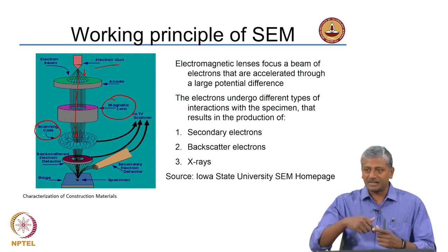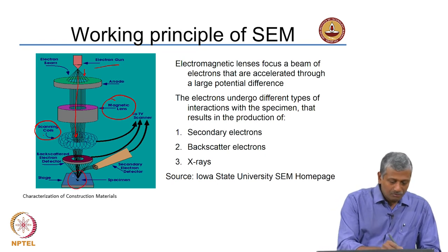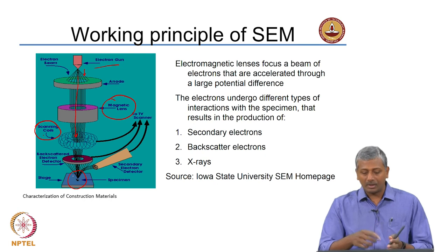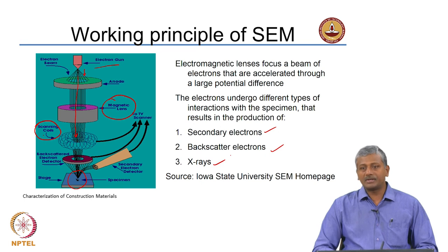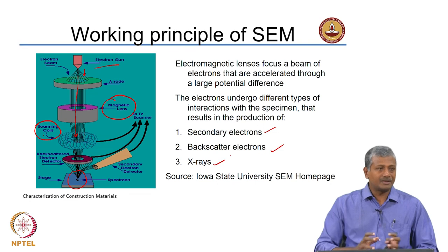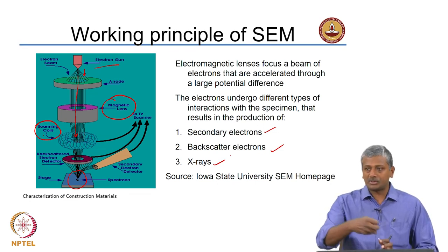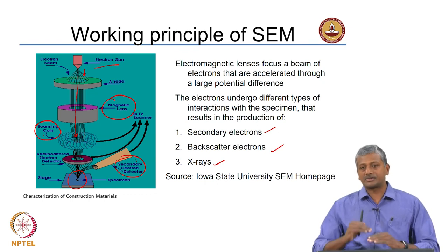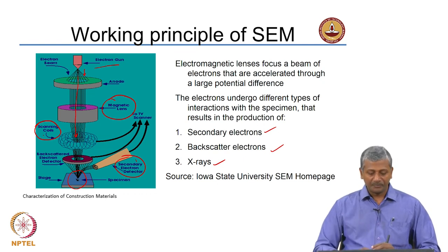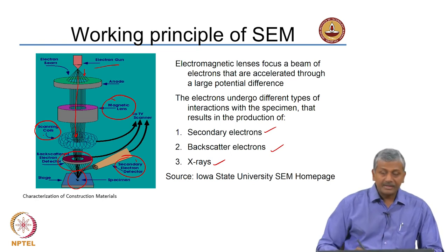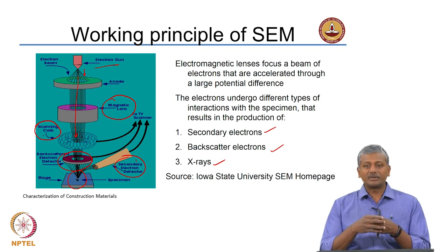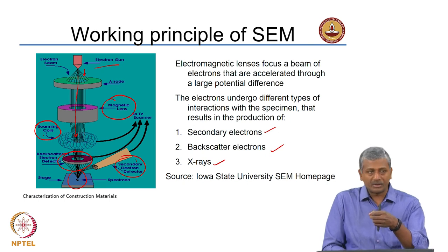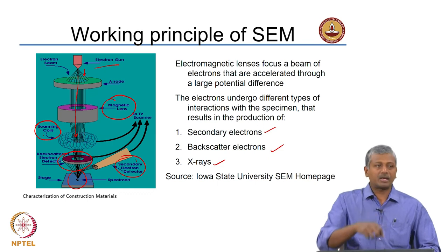As the electron beam scans line by line, interactions between the electrons bombarding the specimen and the specimen itself lead to the generation of backscatter electrons, secondary electrons, and X-rays. These are detected using suitable detectors placed at critical locations around the specimen. The secondary electron detector is placed at a narrow angle because secondary electrons are low-energy. The backscatter detector is placed almost around the optic axis, since high-energy electrons undergo elastic rebound almost straight back up.